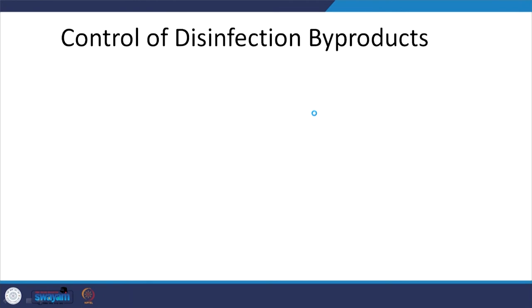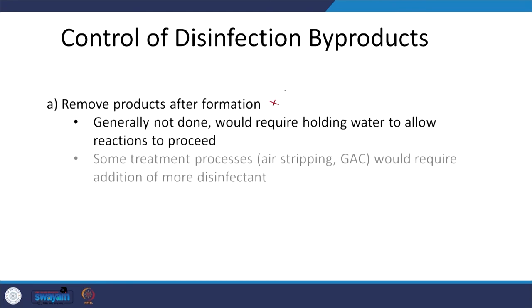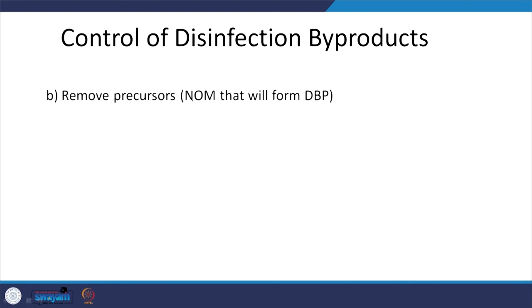Control of DBPs: after trihalomethanes or haloacetic acids have formed, removing them is difficult — options include adsorption of hydrophobic compounds onto GAC, air stripping, or addition of more disinfectant, but these are generally not done as it means creating a problem then trying to solve it. What is done instead is removing the cause — the precursors. Since Cl₂ plus NOM leads to DBP formation, we target the NOM and remove it. That is the remove-the-precursor approach.